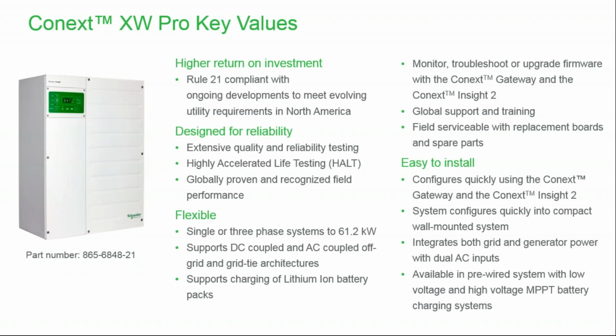So the key values are basically, we feel that we have a higher return on investment with the Rule 21 compliant systems, where we do a tremendous amount of testing for reliability. We can do just about any kind of battery-based inverter connections that you like, from DC coupled to AC coupled, various architectures with lithium-ion batteries. We can do fairly detailed monitoring. We can troubleshoot and upgrade firmware with the Conext gateway, and the units are field serviceable.